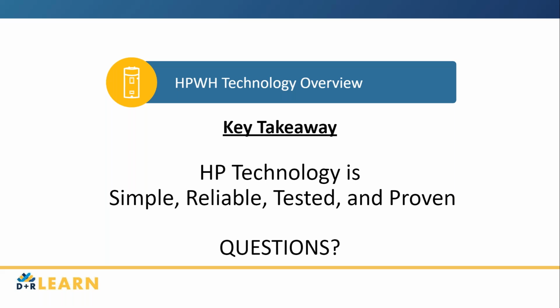Very little. Here's the example that people use when they try to demonstrate this. There's one exception, and we're going to talk about this later in the presentation, but the heat pump water heater compressor only runs generally between 5 and 7 hours a day under normal circumstances. The impact on your HVAC system, what you're getting at, I think, is that your HVAC system is going to have to make up for that heat that the heat pump water heater has taken out. Well, the heat pump water heater is using it at 300% efficiency. So it's not using a lot of energy, even in a cooler space. So you're not going to be penalized too much.